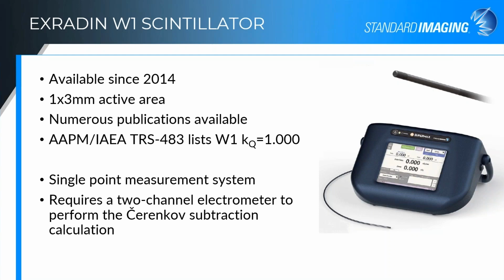The disadvantage of the W1 is that this really was designed to be just a single point measurement system. We were targeting output factors with this first device in order to allow people to measure the output of these small fields. The other disadvantage or limitation is that it does require a 2-channel electrometer, such as our Supermax, in order to perform those Cherenkov subtraction calculations. So the W1 is the fiber itself and a connected shielded optics to convert that optical signal into an electrical current. It has 2 triax outputs, one for the green portion of the spectrum and one for the blue portion of the spectrum, and that's what needs the 2-channel electrometer to read in those 2 signals separately.